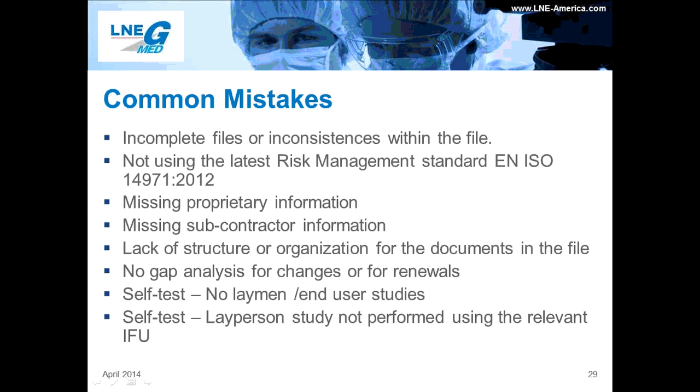Finally, let's examine some common mistakes that are typically seen during the review of technical files. First, we receive incomplete files all the time, and this is potentially the most costly mistake manufacturers can make. Having to request additional information and set up time for additional reviews can add significant amounts of time to your review. GMED provides a list of documents to be included in the assessment. However, when in doubt, you can always contact your notified body representative. In our case, that would be your certification project manager.